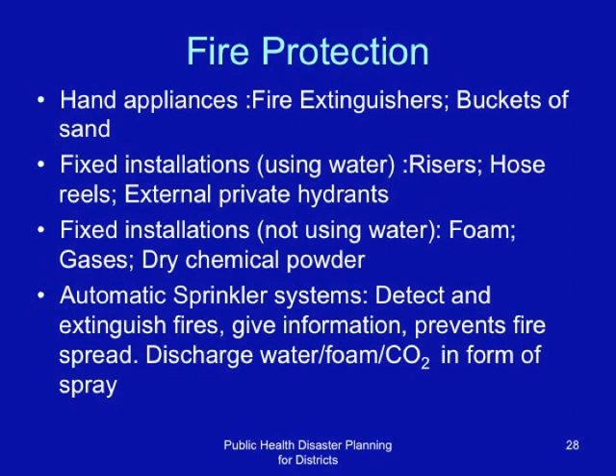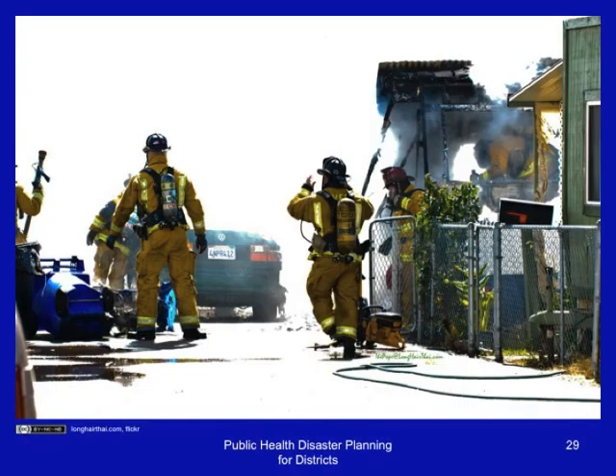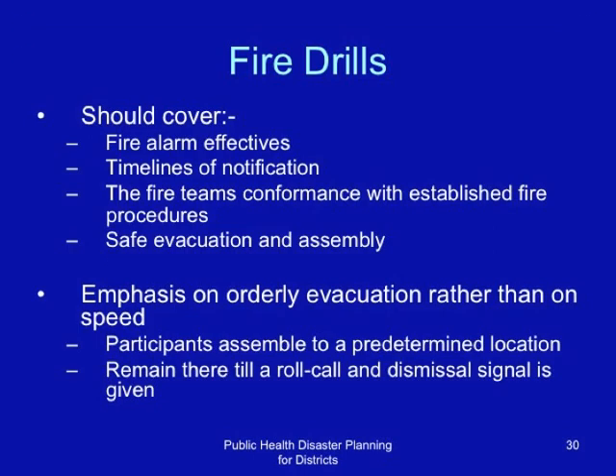Fire drills should cover fire alarm effectiveness — whether a physical alarm is installed or we depend on a human alarm — and this should be tested. They also cover timeliness of notification, fire teams' conformance with established fire procedures, and safe evacuation and assembly. Emphasis should be on orderly evacuation rather than speed.